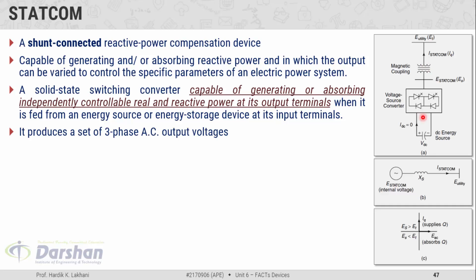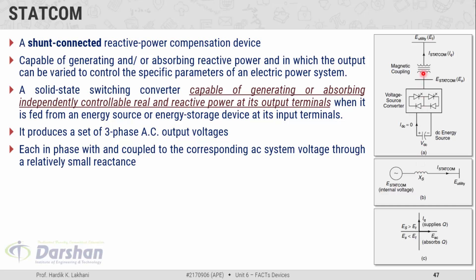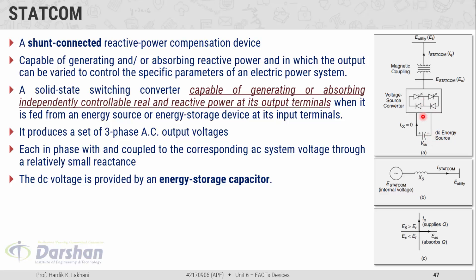The voltage source converter is essentially an inverter — it converts DC parameters into AC parameters. It produces a set of three-phase AC output voltages, each in phase with and coupled to the corresponding AC system voltage through a relatively small reactance. That reactance is offered by the magnetic coupling, i.e., the coupling transformer used to couple the STATCOM to the utility bus. The DC voltage is provided by an energy storage capacitor connected at the input of this voltage source converter.